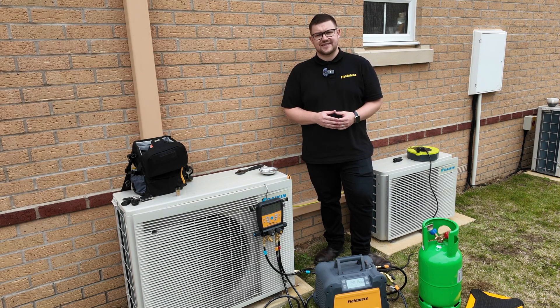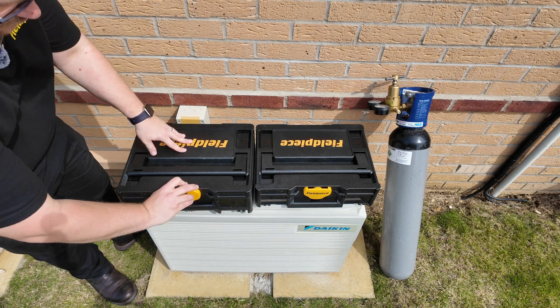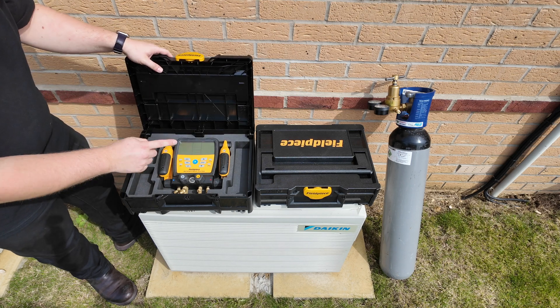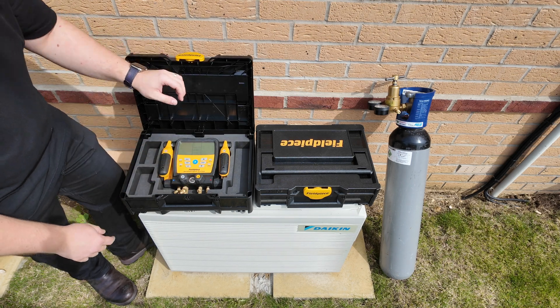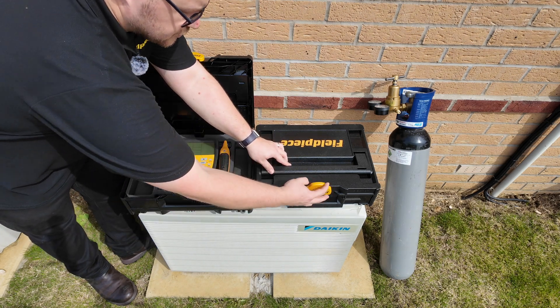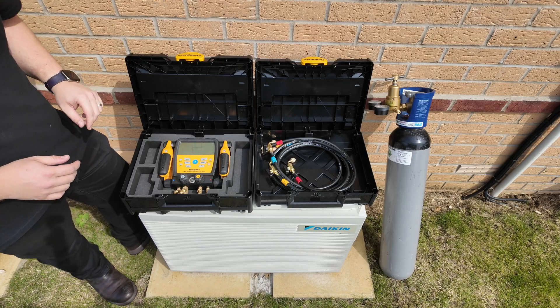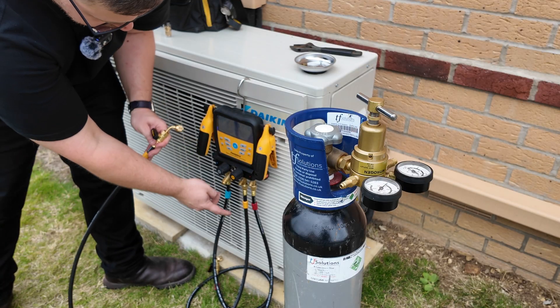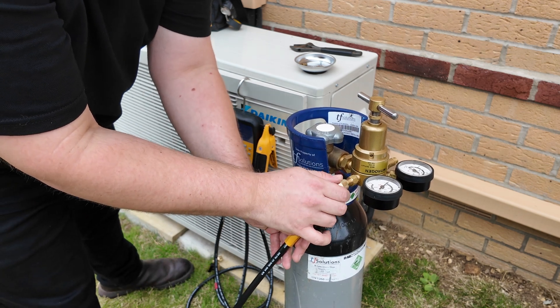Next up it's time to pressure test. In order to carry out a pressure test we're going to need some tools. Firstly we're going to need the Fieldpiece refrigerant manifold and the two temperature clamps, some Fieldpiece hoses and a nitrogen cylinder with regulator. With the manifold still connected to the system I can now connect the yellow hose line to the nitrogen regulator.